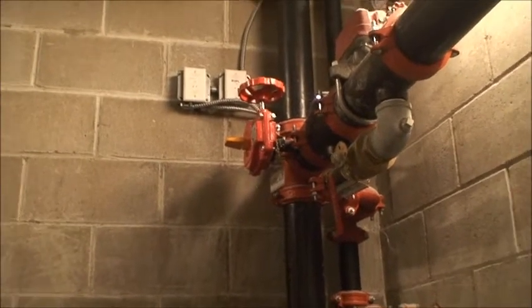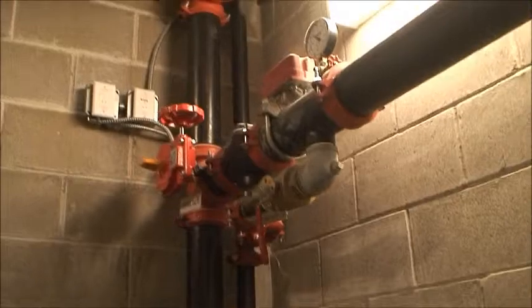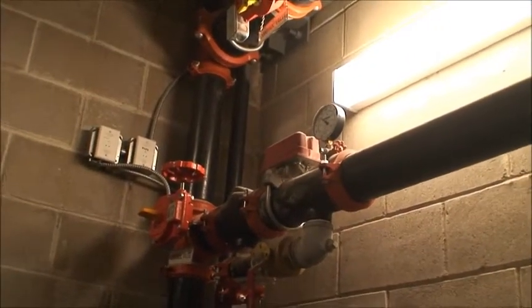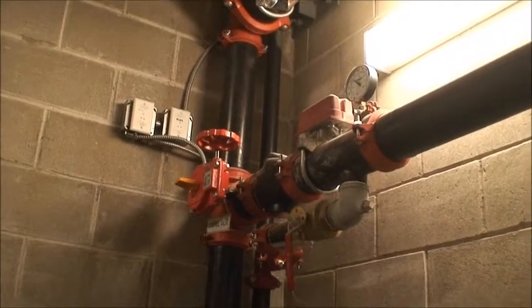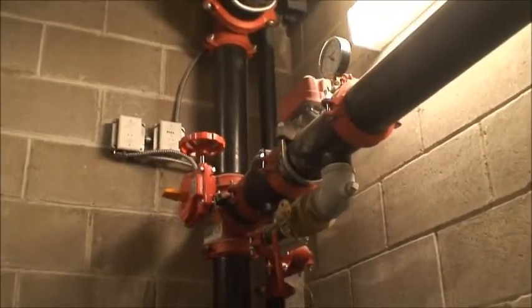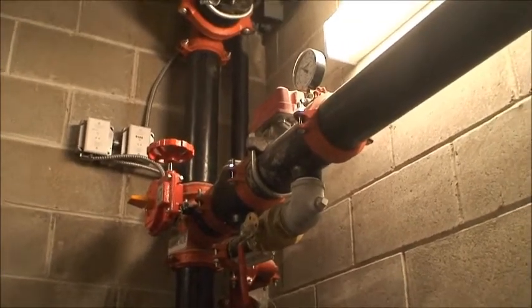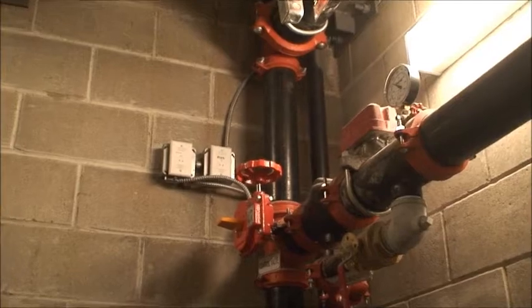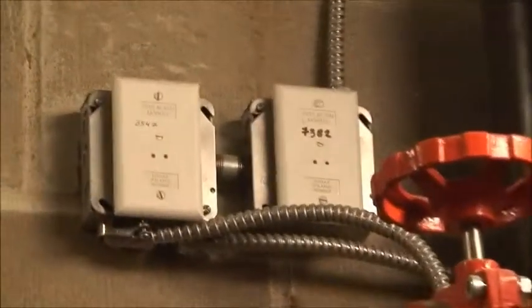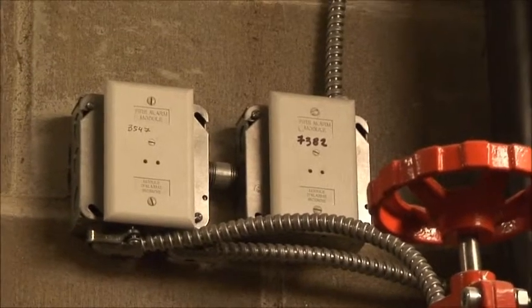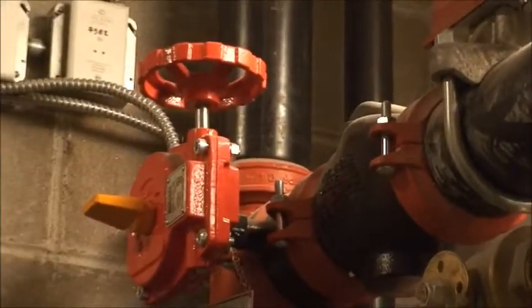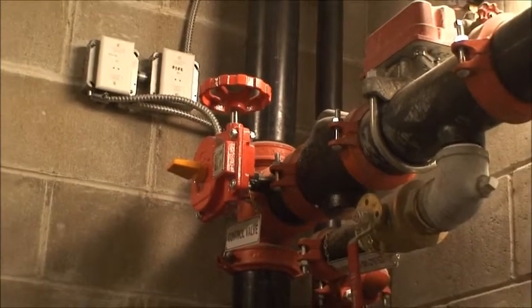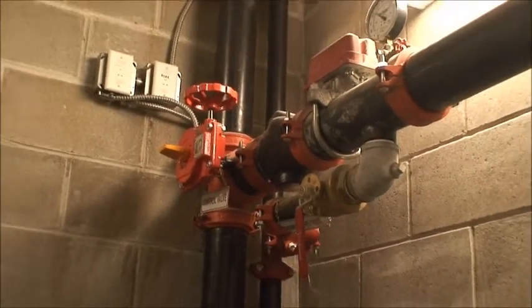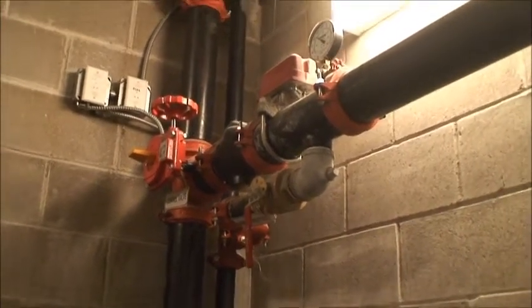In this standpipe is your floor tamper switch and your floor flow switch. If for some reason off of this run, I believe this is the mezzanine, which is connected, I believe, to the restaurant as well, there was a flow, it would go into alarm, would activate one of our modules, and we would get an alarm with any sprinkler. If someone was to come and close the tamper switch, the panel will be alerted with a supervisory signal. It won't go into alarm, but you are impairing the system by closing that switch.